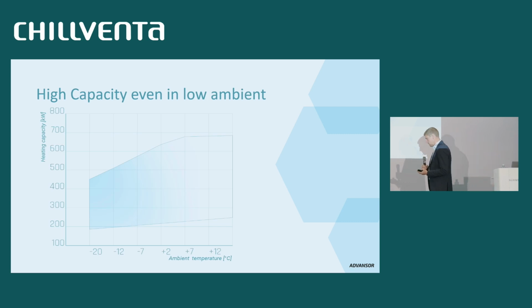As I said before, we can operate down to minus 20 degrees ambient temperature, even with high heating output. So this plug-and-play heat pump at plus 7 degrees delivers almost 700 kilowatts of heating. And if we look all the way down to minus 20, we can still deliver more than 450 kilowatts of heating. We can still provide 85 degrees supply temperature, even at minus 20 degrees ambient temperature. I know there are not many places where we have minus 20, but it really shows the capability of this product.